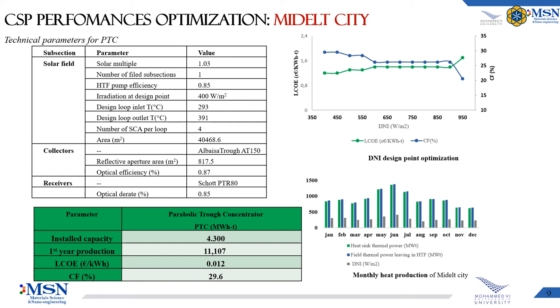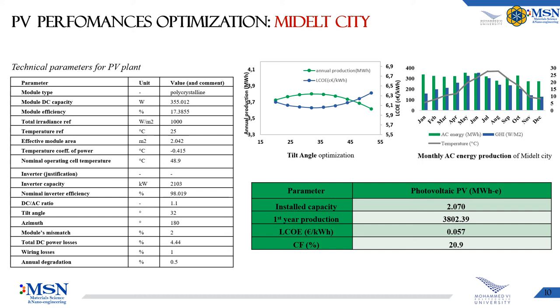The DNI design point is a very important parameter for CSP technology, as it allows finding the optimum size of the system. The optimum DNI design point is around 400 W/m², which yields the lowest LCOE and the highest capacity factor of almost 29.5%. The annual thermal energy production from the solar field simulation using SAM is estimated at around 11.1 GWh thermic, computed using a solar multiple of 1.03 and a DNI design point of 400 W/m². The plant's capacity factor is predicted to be 29.6%, with a levelized cost of heating of around 0.012 €/kWh thermic.